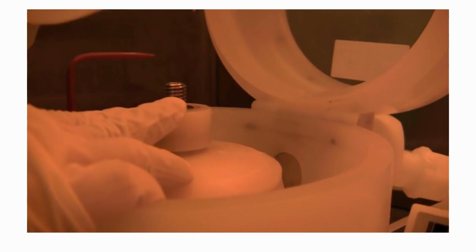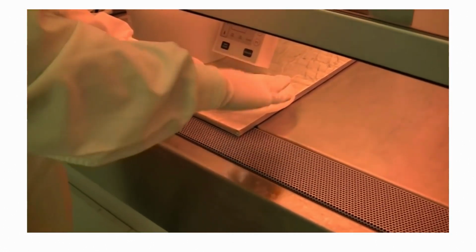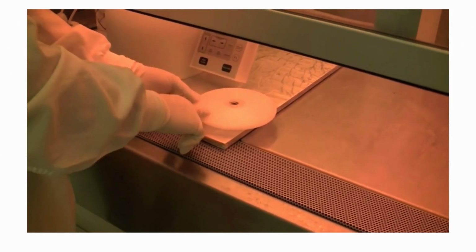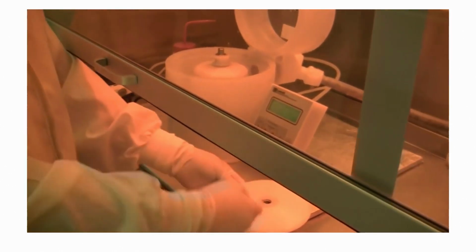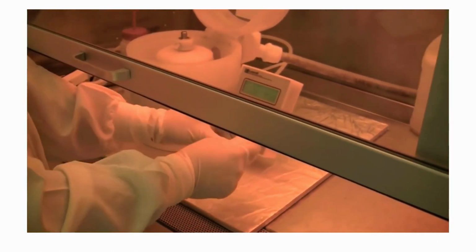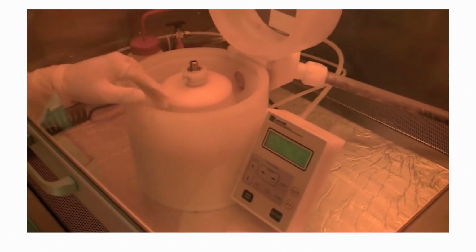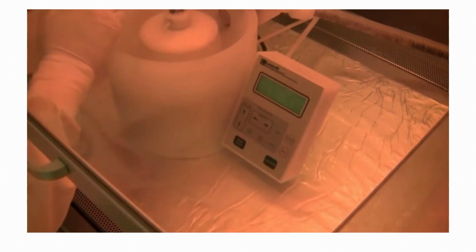and this comes out. Then you can get this out here, and you can spray with acetone and wipe it here safely. Because here it won't get sucked into the motor, and it won't get sucked into the tubing. You don't want to spray it directly on here because it'll get sucked in. So here it's safe. You just drench it, you clean it, you take off the chuck, clean in there too. And then when it's clean and smooth, you can also clean the walls here that are hard to reach and underneath. So you're just going to wipe and wipe it.